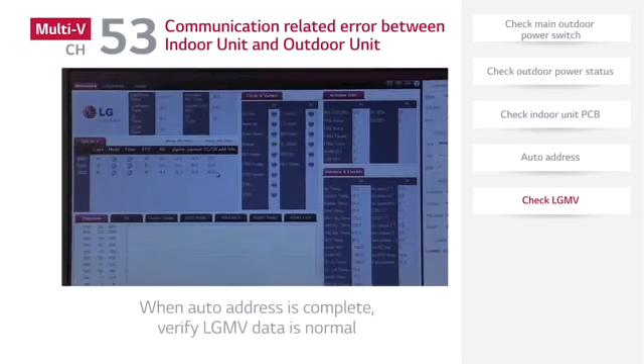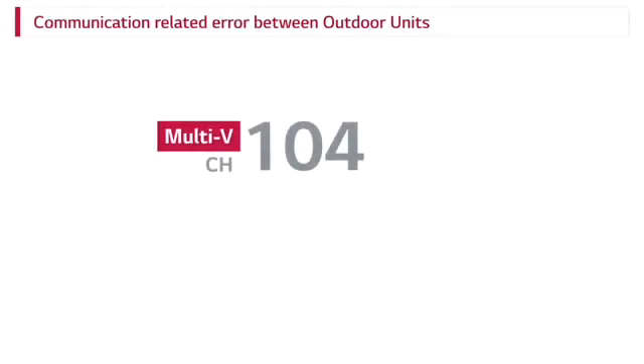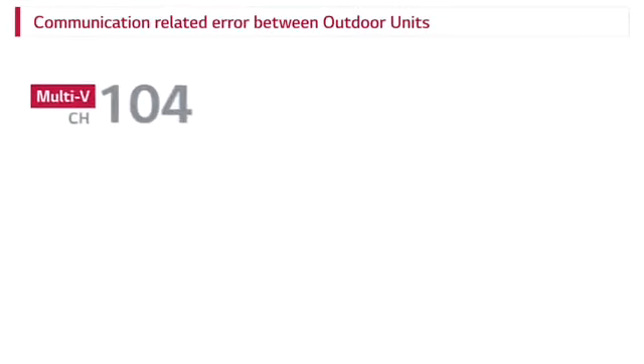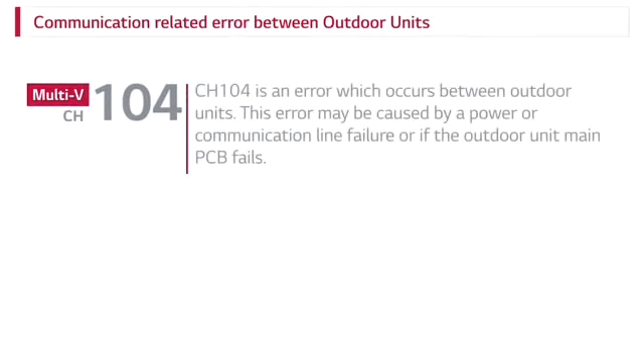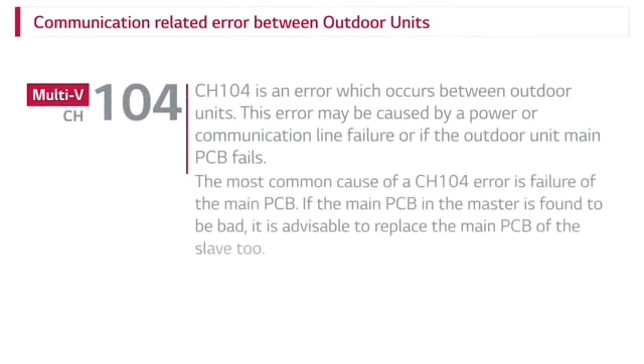When the auto address work is completed, check LGMV data for normal operation. Communication-related error between outdoor units. CH104 is an error which occurs between outdoor units. This error may be caused by a power or communication line failure, or if the outdoor unit main PCB fails.